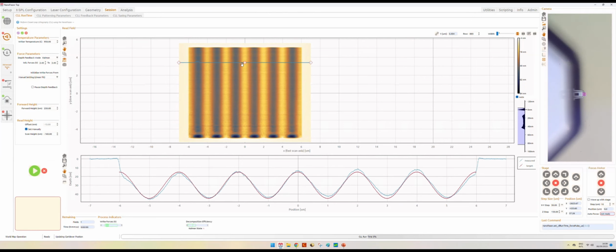In contrast, if we decrease the time in contact with the surface, we're decreasing the amount of energy given, so we're removing less material. This is a quite intuitive way to understand this parameter, and it can almost be compared to a sort of dose parameter that we can regulate with the NanoFrazor.